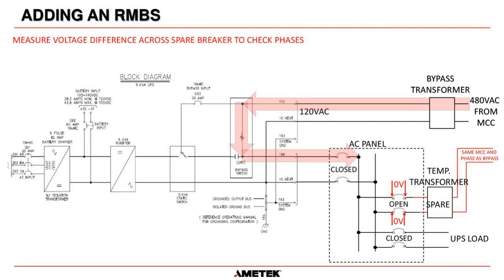Because what can happen is if you chose B phase and C phase here and A phase and B phase here, there is going to be a phase difference. You would have 124 there and 121 volts there, but they're going to be completely out of phase. So you could, let's say, have 180 volts difference across that breaker. If you see that, obviously you're not going to close this breaker in. So just take your time and follow this procedure. This ensures that you're going to maintain the load circuits when we go through the next steps.